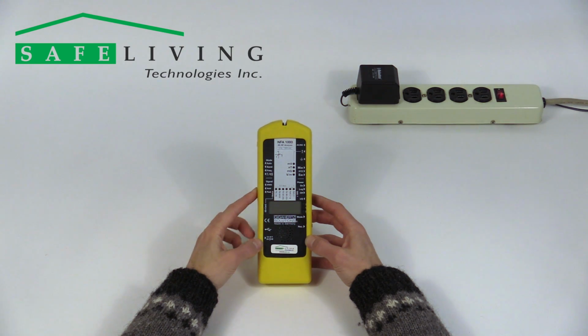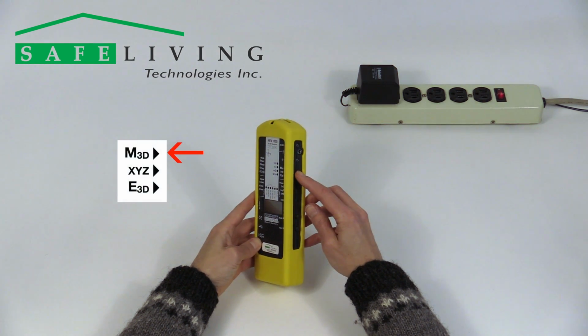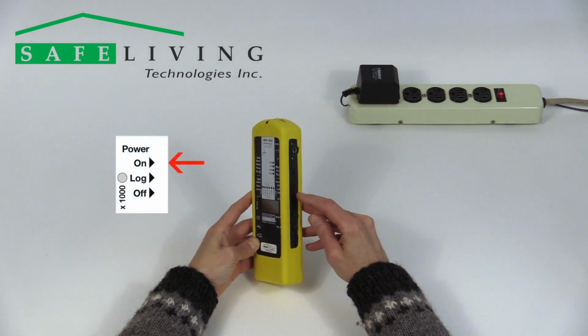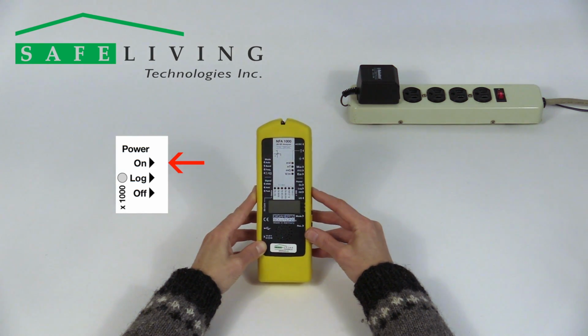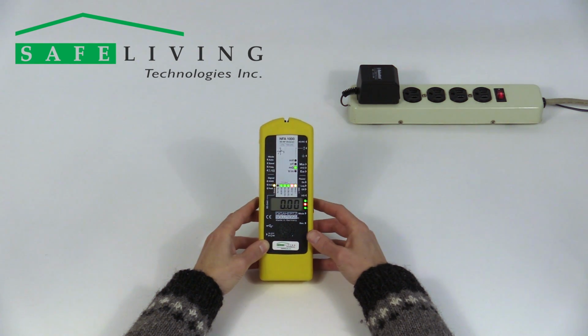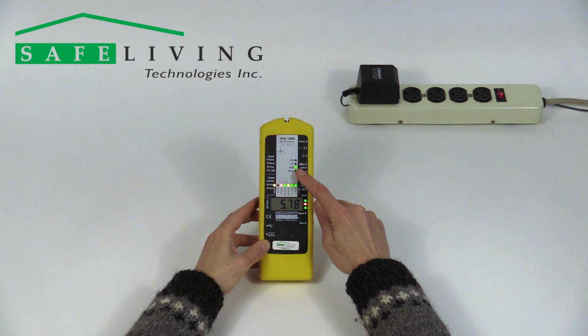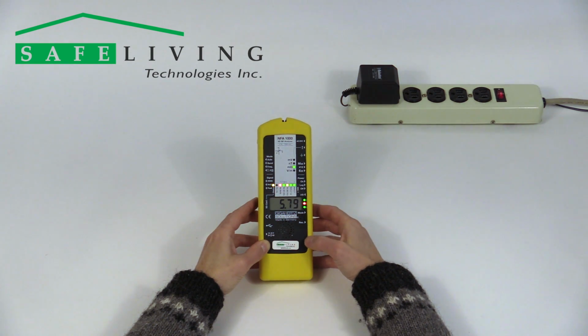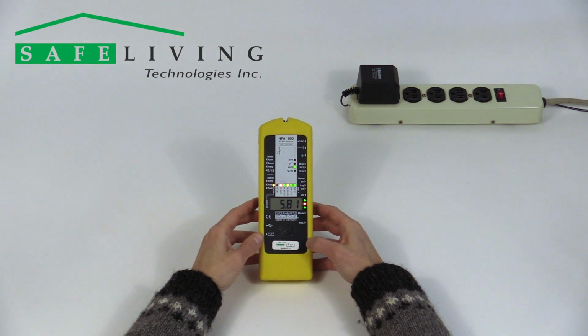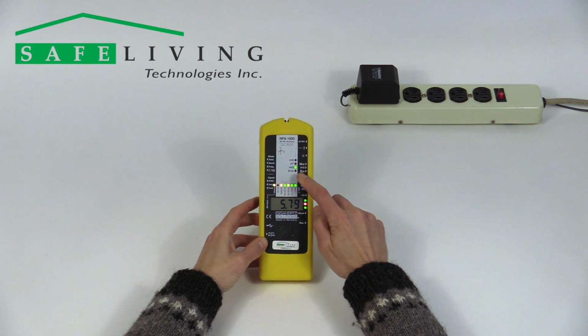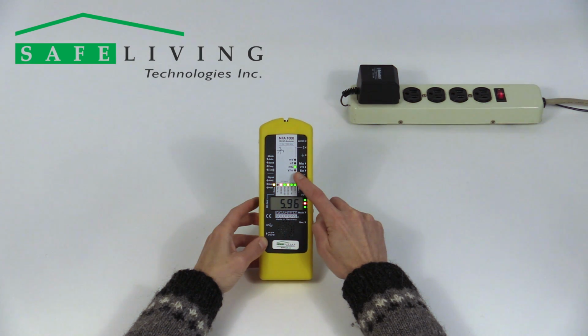Set the field type switch to M3D and power the unit on by moving this switch to the top up position. Note the solid green light showing that you are now measuring in milligauss. If you prefer to measure in nanotesla, this can be configured with NFASoft, which is described in our Datalogging and NFASoft video. Note that the LED beside volt per meter flashes green every few seconds to indicate that a one-dimensional electric field measurement would be measured while logging.